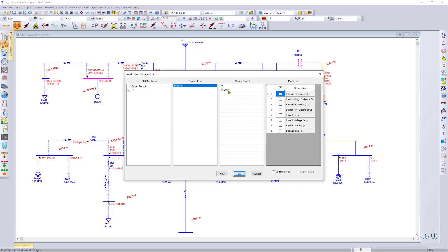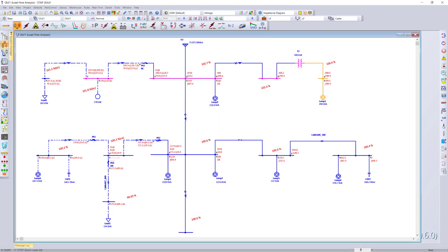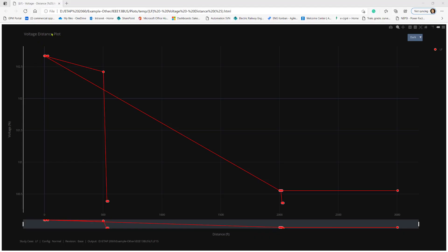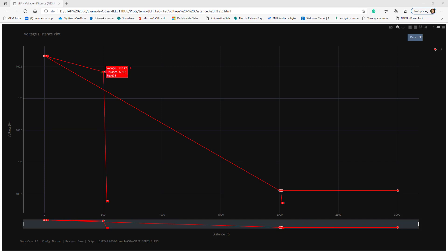Let's go ahead and plot voltage versus distance. What we see is a voltage versus distance plot that gives us our voltage in percentage and the distance in feet. And by hovering on any of these points, you can easily visualize the voltage, the bus ID, as well as the distance from the swing source.